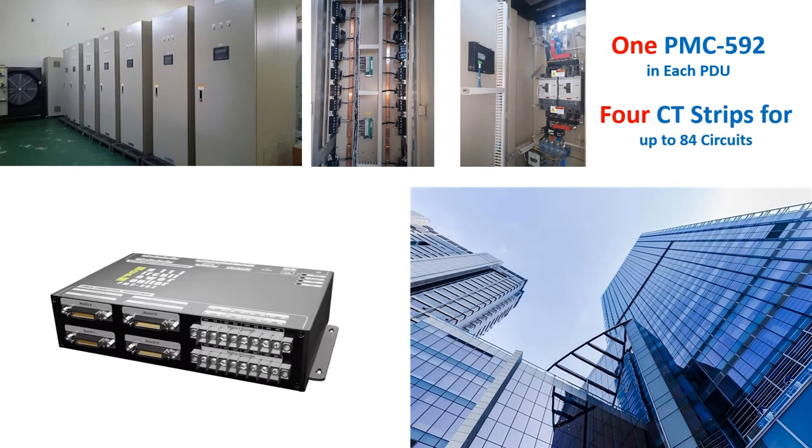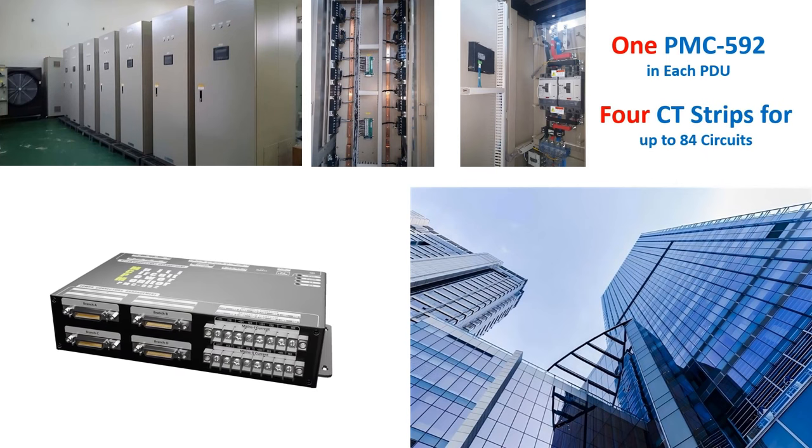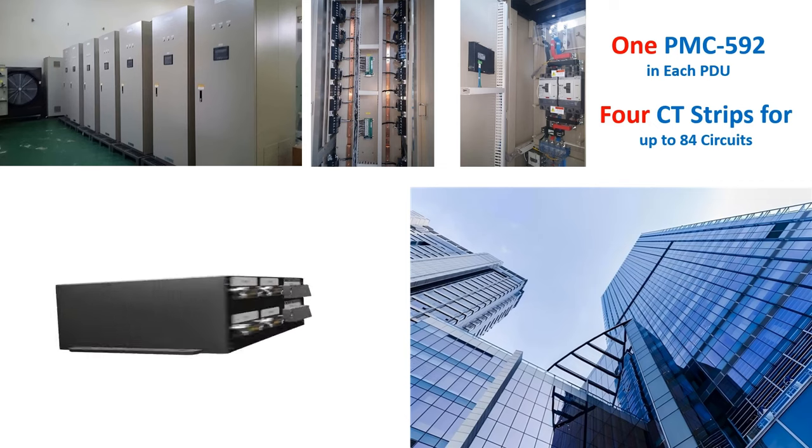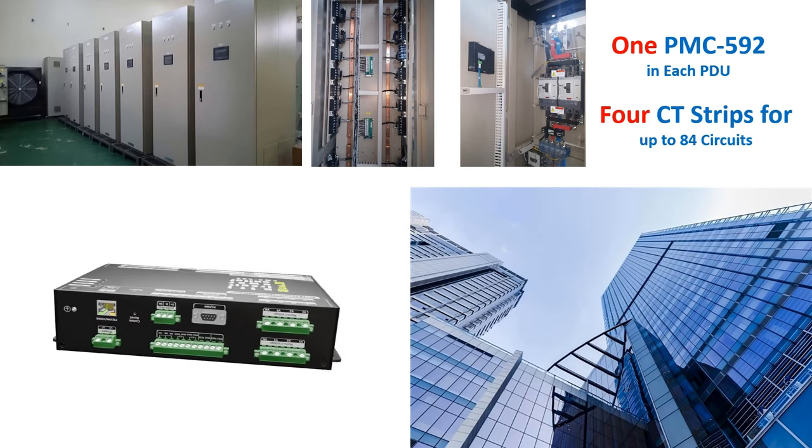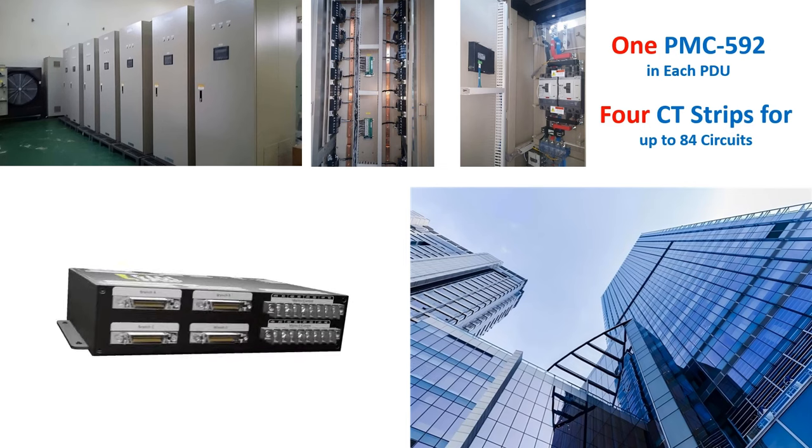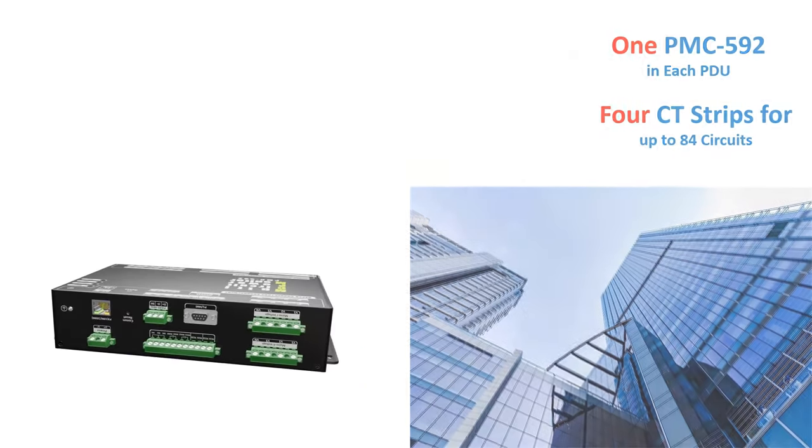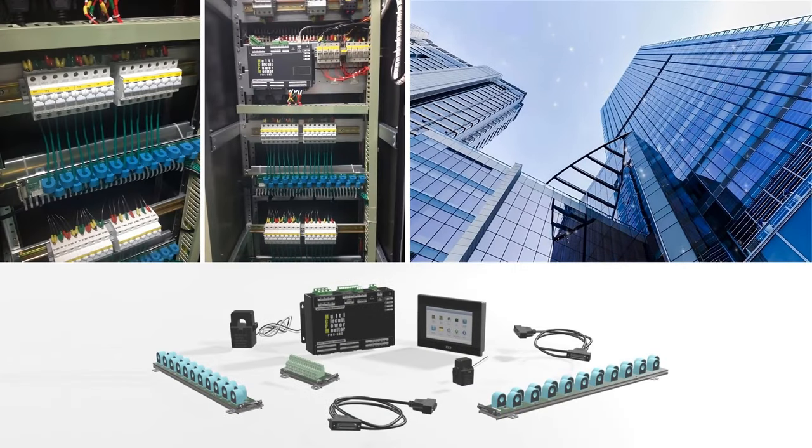CET's PMC592 was proposed as a solution. Each PDU was installed with a PMC592 and four CT strips for monitoring up to 84 low-rating circuits, whereas on all main feeders to data centers, high-rating split-core CTs were used to avoid scheduled outages. The PMC592 not only fulfilled all the customer's requirements, its performance on dip swell detection with waveform recording capability and support for sending measurements or alarm data via SNMP have made it one of the most satisfied multi-circuit power monitors in the market.